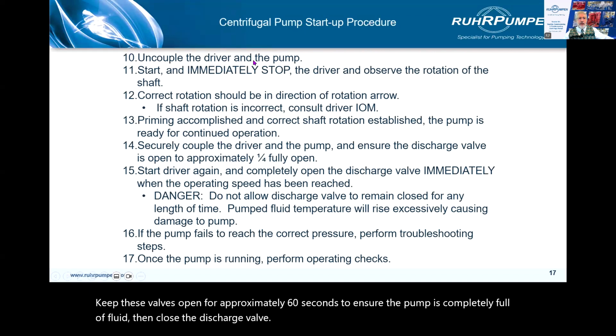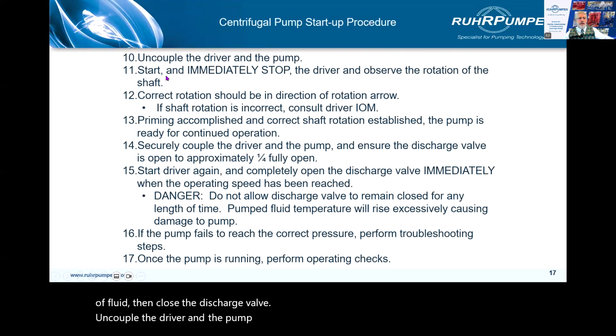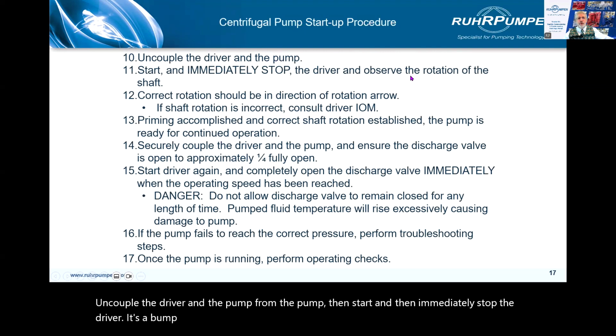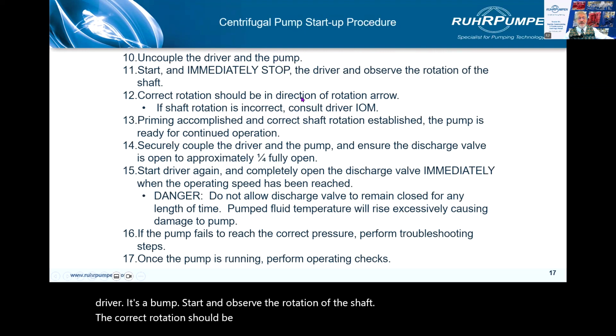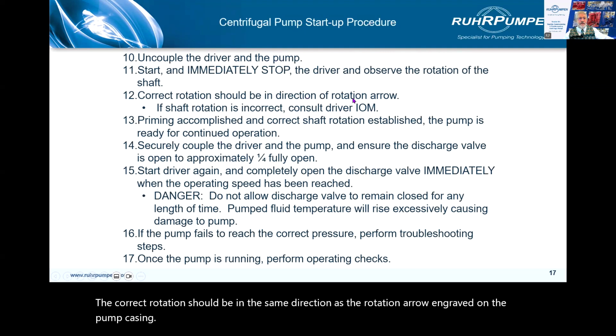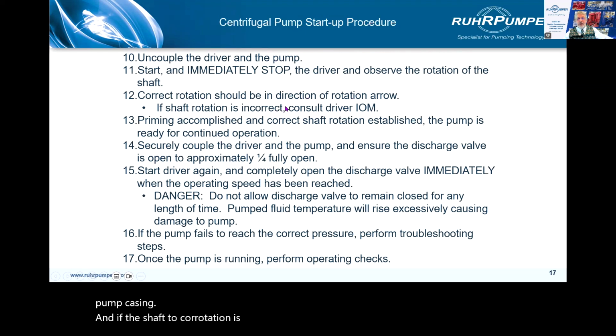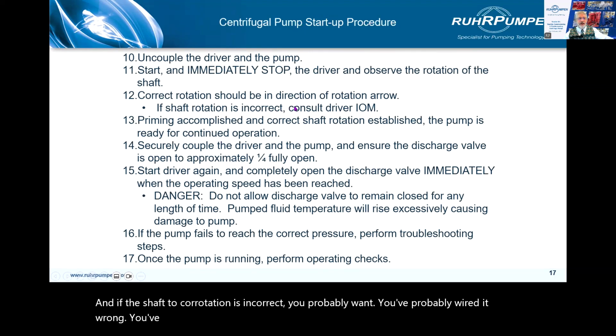Uncouple the driver from the pump, then start and then immediately stop the driver. It's a bump start, and observe the rotation of the shaft. The correct rotation should be in the same direction as the rotation arrow engraved on the pump casing. And if the shaft rotation is incorrect, you've probably wired it wrong. You've probably switched the live and neutral.